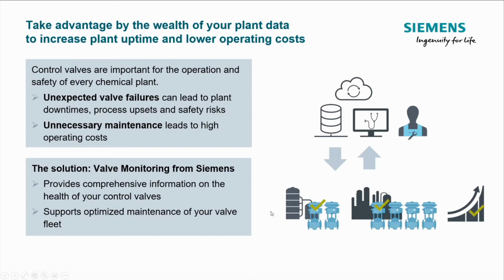Now I know power stations are really critical, and the company that was coming out and testing that valve were just moving that valve manually up and down and making sure that it moved. They weren't doing any advanced diagnostics. And the beauty of it is, the likelihood is, especially if you've got a Siemens valve positioner, you've got something on there that's continuously monitoring your valve performance. So as long as you record that and action it, you can probably stop maintaining all of your valves and stretch out your maintenance on your critical valves.